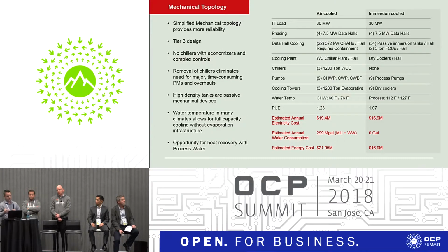The mechanical topology, those of you who have designed, built, operated, lived in the baseline case, you know about all the compressor maintenance that has to be done on the chillers, all the water treatment that has to be done with the condenser loops. There's a lot of equipment in there, a lot to deal with. So in the immersion cooled situation, we've gotten rid of all the compressors. We've gotten rid of all of the CRAH units. We've gotten rid of all those fans associated with it. The tanks themselves have control valves which modulate to maintain the liquid level and the temperatures within the tanks. So that's how you're handling all of your heat within the space.